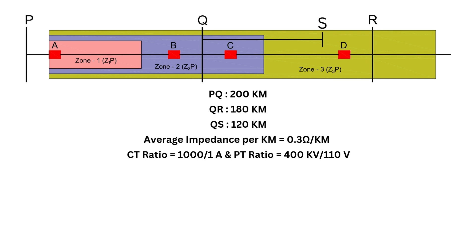Let's calculate the setting for zone 3, which provides backup protection for the longest remote line. Since the line from Q to R is 180 kilometers and it's the longest line from Q, the total length we need to consider is PQ plus QR = 200 + 180, which is 380 kilometers. The impedance becomes 0.3 × 380, which is 114 ohms.